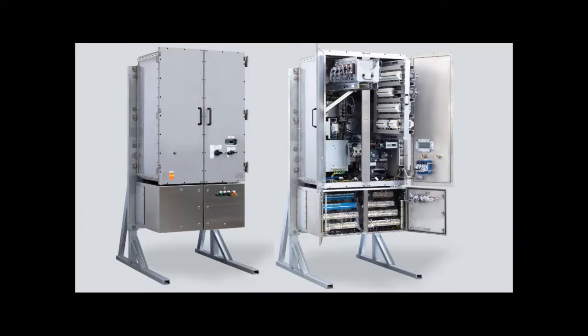There's also the visual indication whenever there is an explosion. With a typical EXD box, the only way you're going to see if there has been an explosion is if you are doing your inspections and maintenance and you have opened up the enclosure. There are many companies where, such as during times of COVID, the reduction in inspections and maintenance was done as a cost-saving measure.